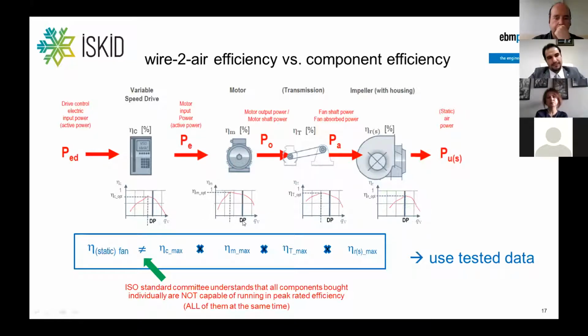DP stands for duty point. That's just to explain a little of what I'm saying here, and that's why in some of the standards a so-called correction factor of 0.9 is used. When you multiply all the components and then apply the factor 0.9, you will get quite close to the fan static efficiency or total efficiency.